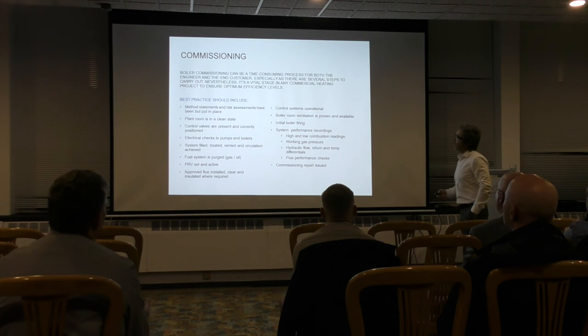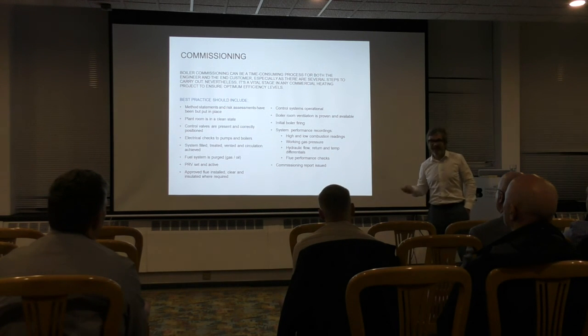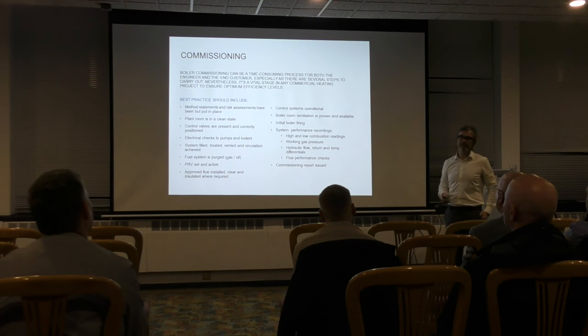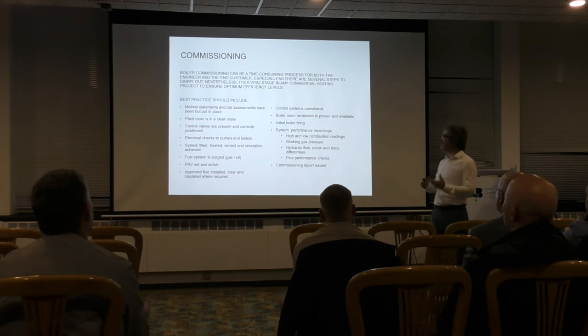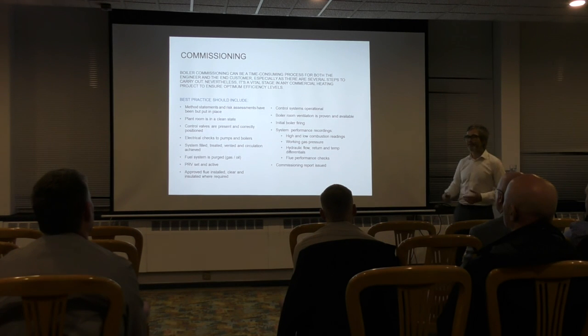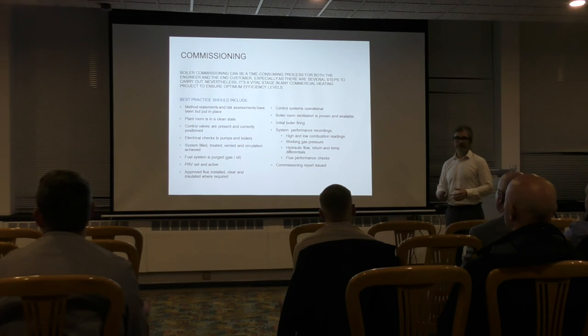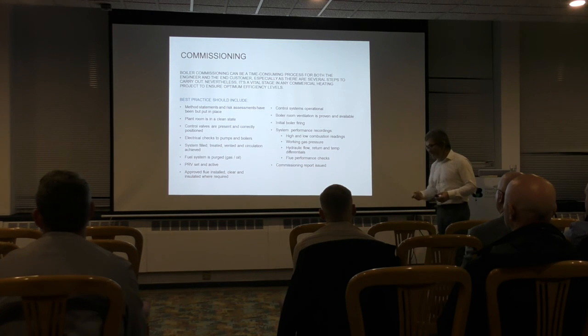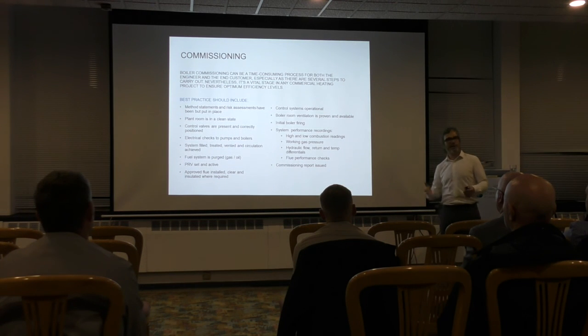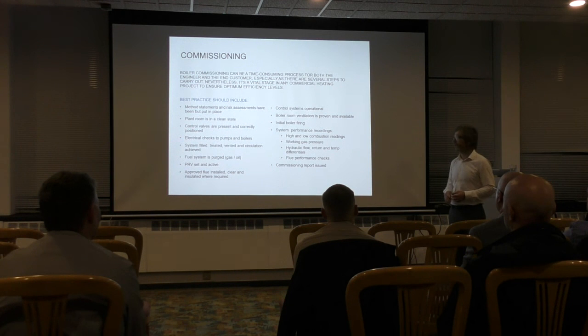Method statements, we spoke about that earlier, method statements and risk assessments. Again, that's always good to go all the way down the line to the commissioning engineer. So if you can do that, then he knows what he's up against before he gets to site. Is the plant room in a clean state? All these things seem pretty obvious, but you'll be surprised how many times we go to site. An engineer sent me a picture a few weeks ago of a site he went to commission, and he wrote "dust on top of the boiler". He said he just can't do it. The plant room was so dusty, and it just wouldn't have been good for the boilers to be firing in that environment.